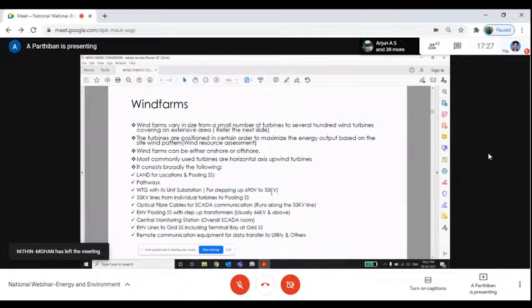We can switch the turbine off, we can switch it on. Some operations can be done from here itself. Some error attending and breakdowns can be attended from the CMS itself. So for that only this OFC cable is used, because all this communication from the WTG to the central monitoring station is taken through this OFC network only.